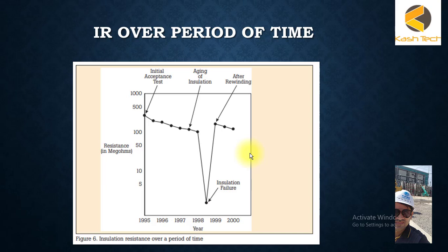The third thing is when you're doing this megger testing, you have to do it above dew point. You should avoid extreme humid conditions as it will not give you proper readings. Another thing we discussed is that applied voltages for maintenance testing are way less - in fact, they are less than the rated AC values. The IR in DC, as compared to installation testing, which is 2 times plus 1 kV.